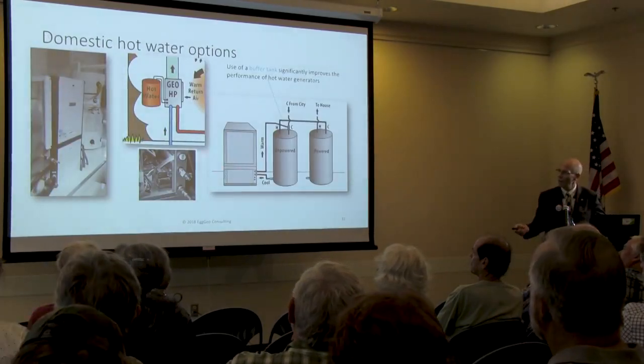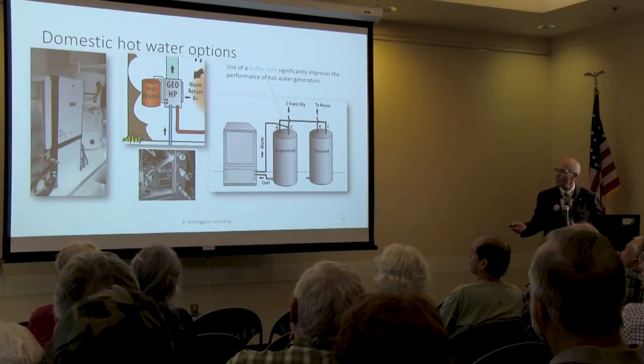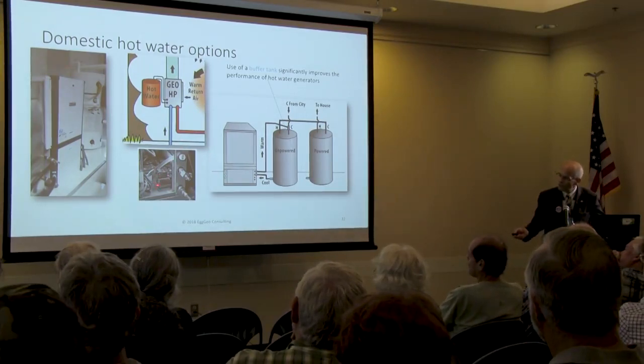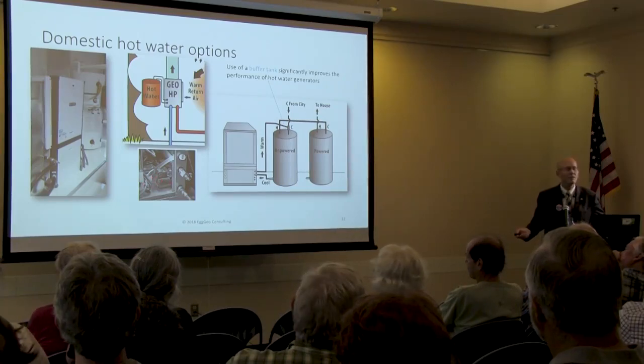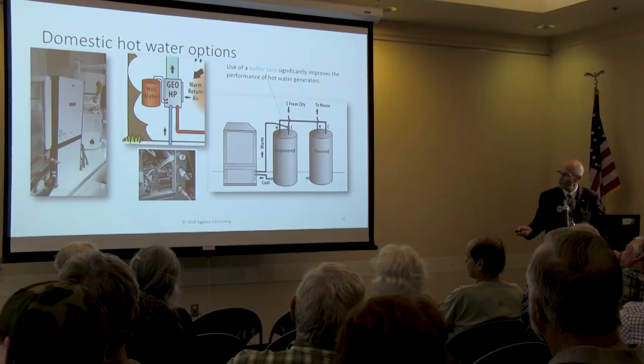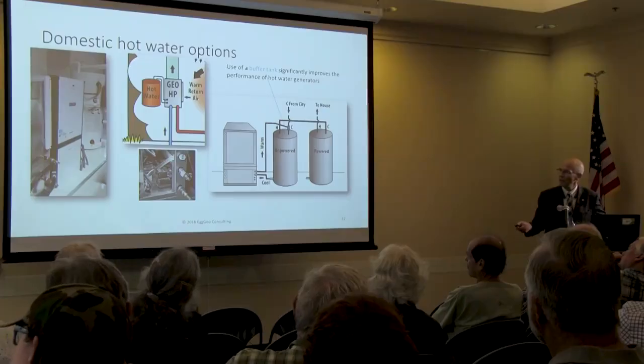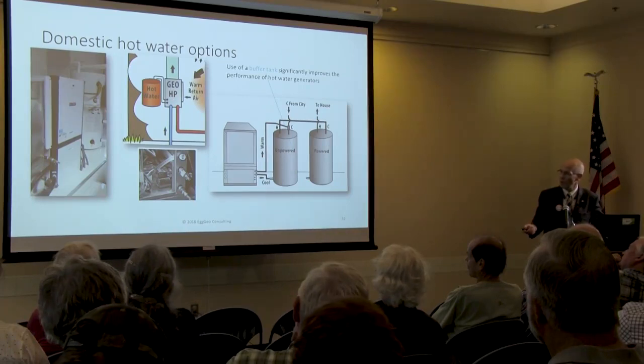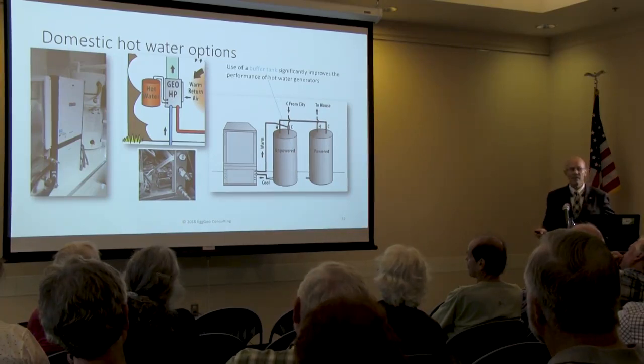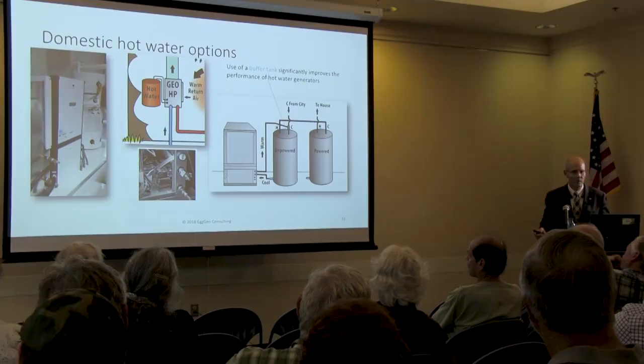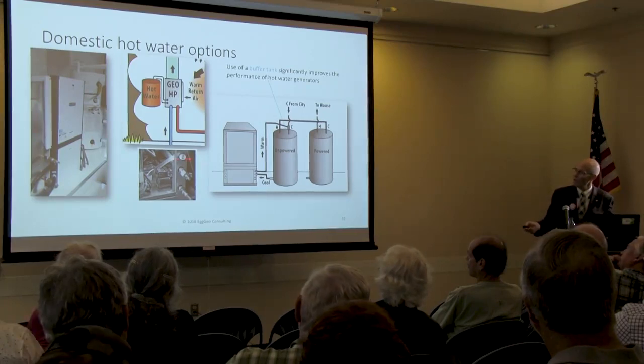I talked about the domestic hot water generator. You can actually see the circulator that's in most heat pumps. This is an option, by the way. It's usually a couple hundred dollars on a heat pump to get a domestic hot water generator. What it does is it takes the waste heat that the compressor is creating anyway, and it pumps all of that heat in the form of domestic hot water into the water tank. And even in the winter time, it will take the first couple or 3% of superheat, as they call it, off the compressor, and put it into the tank. And yes, that costs you, but it's pennies on the dollar compared to what it would cost to heat with gas or electric. So that's how it's tied in.